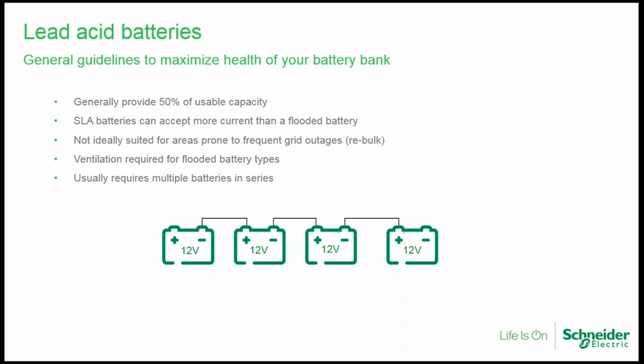Lack of regulation when AC coupling may result in a reduced life cycle of lead acid batteries when the application does not provide a regular 3-stage charge. Some battery warranties are contingent on the batteries receiving a full charge regularly. Lead acid batteries work well in grid-connected AC-coupled applications, especially if used as a standby battery. When cycling the batteries daily, for example in time-of-use applications, it's important not to allow the batteries to discharge below 50%, especially if they're sealed. Flooded batteries are more forgiving because they can be equalized to recover their performance. Lead acid batteries are only good for approximately 1,000 cycles, and only if they're not misused.